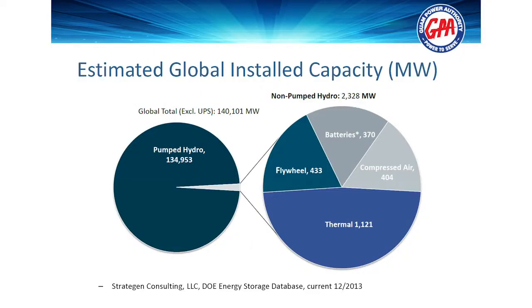Next. This kind of gives you an idea of where you are. In the world of energy storage, it's dominated by hydro, right? Pumped storage hydro dominates the storage market. You can see as you go into this, flywheel, batteries, compressed air, and thermal. In an islanded system, you're seeing more and more applications of batteries and flywheels. We have a small system in Alaska. It's about 26 megawatts. It soon will be 100% renewable. 6 megawatts of wind, 3 megawatts of batteries, 2 megawatts of flywheels, and 20 megawatts of hydro. It's a pretty state-of-the-art system. It's a combination of flywheels and batteries. Next.